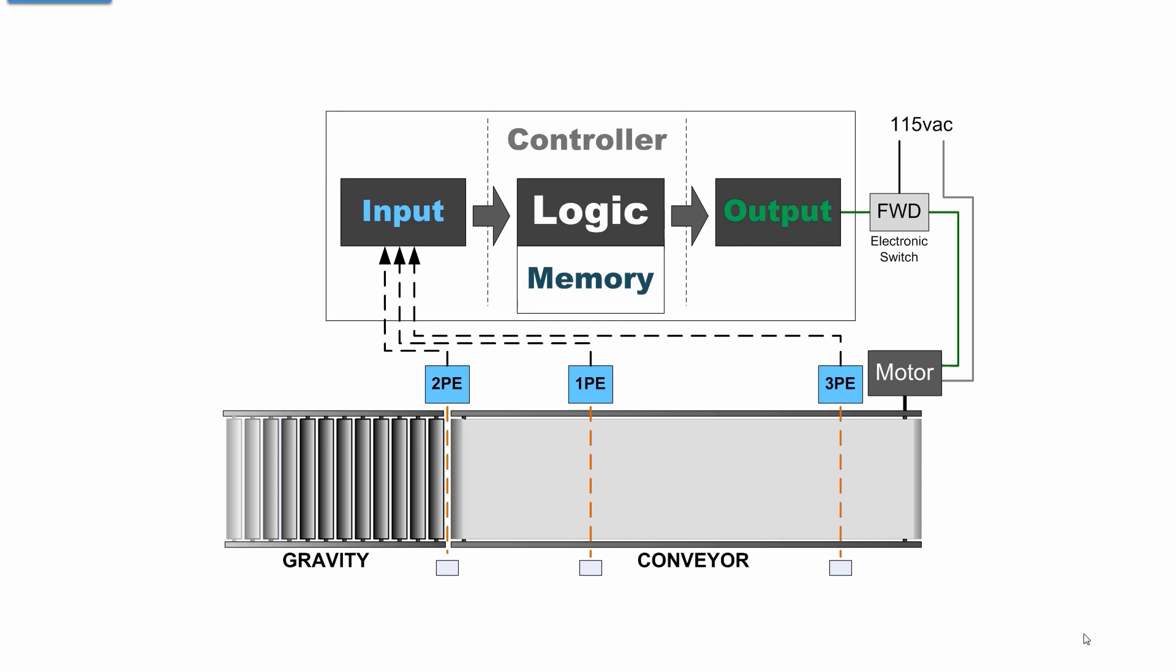Here we've expanded our input to three positions on the conveyor belt. A controller has to have a photoelectric sensor or some sort of sensor for every single position. Here we have three. So if we have a carton come down the gravity feed conveyor, 2PE, photo eye 2, tells the controller that there is a carton available to come onto the conveyor. At that point, the conveyor can then pull the carton onto the conveyor until it blocks 1PE, photo eye 1, and then it stops.